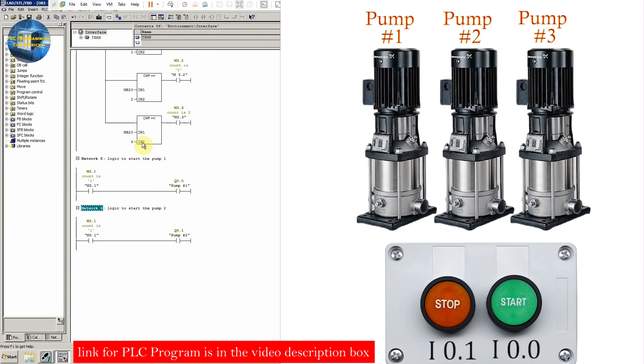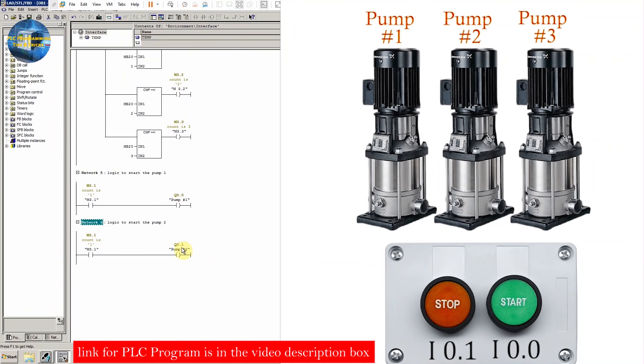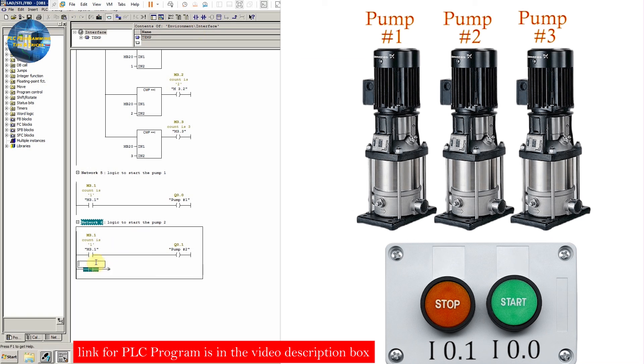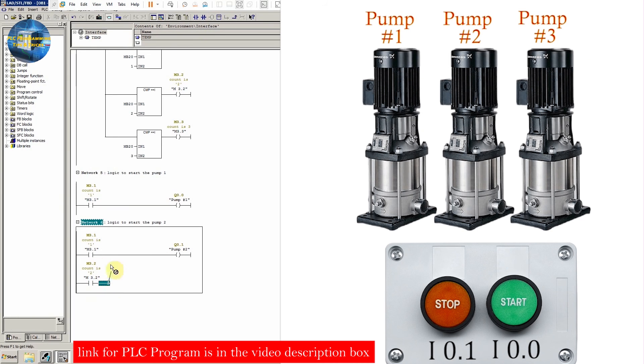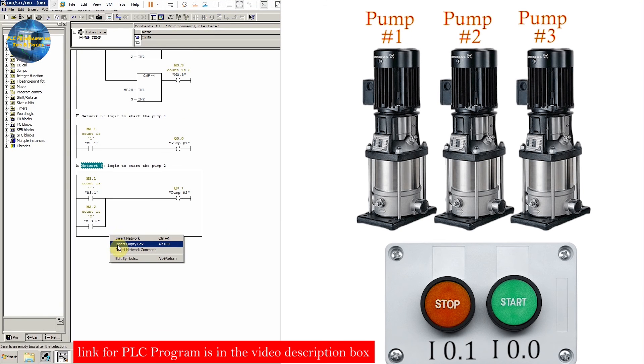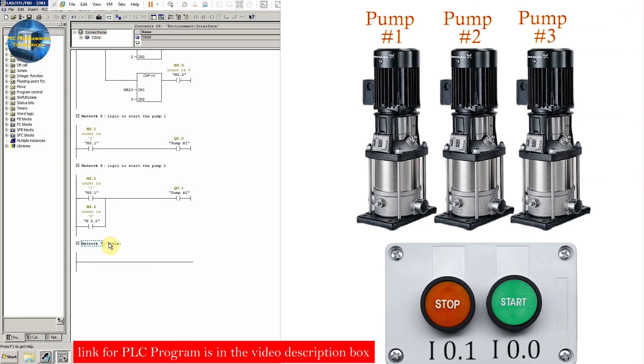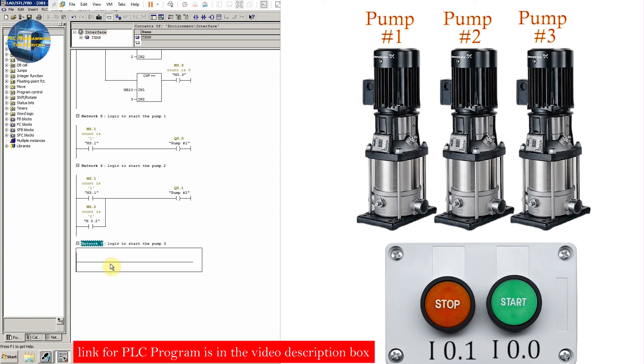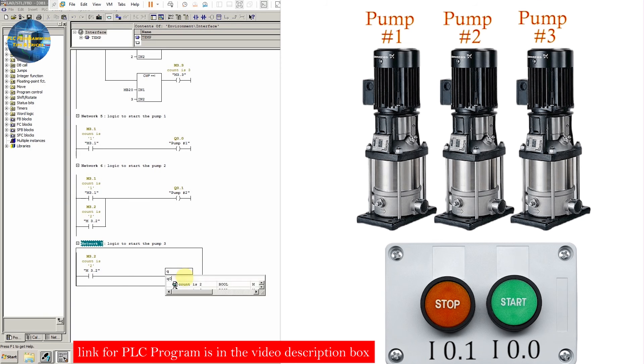Whenever the count is 2, we also need to start pump number 2 and pump number 3. So we insert a parallel contact with M3.2 in the pump 2 network — whenever the count is 2, it will also start pump number 2. We insert another network with a NO contact of M3.2 to start Q0.2, which is pump number 3.